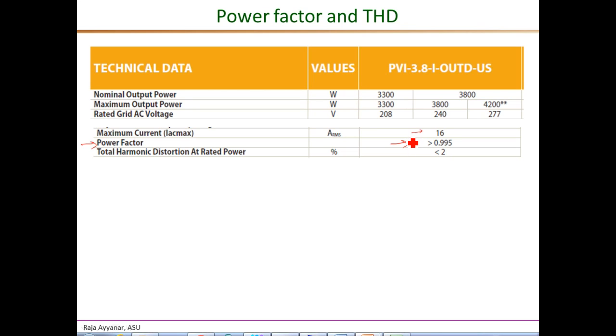Even though inverters are four-quadrant devices capable of operating at any arbitrary power factor, and this capability can be used to provide reactive power support or voltage support to the grid, at present standards like IEEE 1547 do not allow string inverters to actively take part in voltage regulation. But in the near future it may become a standard feature for inverters to provide reactive power and voltage support to the grid, especially when they are not operating at full rated power under lower solar irradiance conditions.